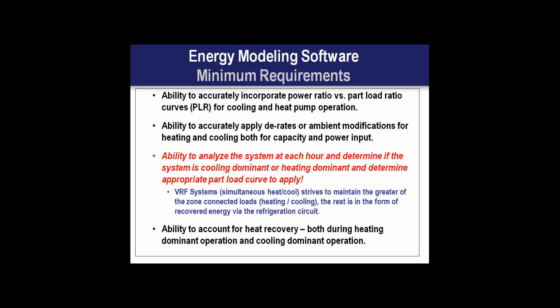So when looking at energy modeling analysis tools, there are some bare minimum requirements. This is by no means all inclusive. There are other factors and derates that have to be considered on top of this, but these are bare minimum points that have to be incorporated into an analysis tool. The first is the incorporation of PLR curves, or part load ratio curves. You'll see a part load ratio curve for cooling performance when the VRF system is in cooling, that's percentage of full power based on percentage of full load. And you'll also see a similar curve for heating operation.